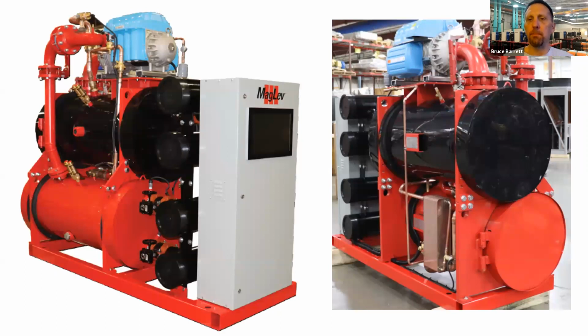All right, so the picture on the right-hand side shows the condenser water box, which is hinged. So undo the bolts, swing that door open, do your tube brushing, annual maintenance. You can do that one at a time. You don't have to do them all at once, so it doesn't become a shutdown opportunity. If you have a low enough load, you can get in there and clean your tubes.